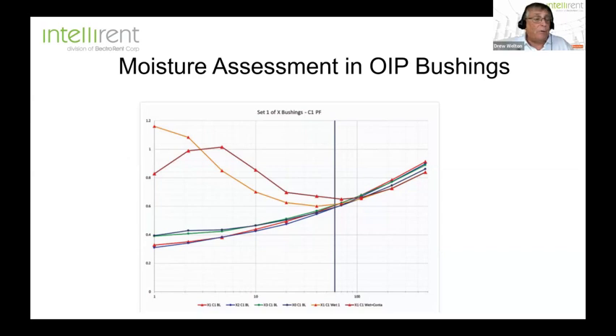When you test bushings, you do your visual inspection. You might, like Mark said, check for heat. You might take a thermal measurement and look for excessive heat in the bushings while the transformer's online. But basically, you do your C1 test, your C2 test, or a hot collar test, and you compare that to the nameplate rating. If you don't have the nameplate data on a C2 test, you compare one to the other. But when you drive that frequency down, you can see here, on these C1 measurements, that on 2 of the bushings there's an indication of conductive losses in the bushings themselves. So you can run this test on bushings also.